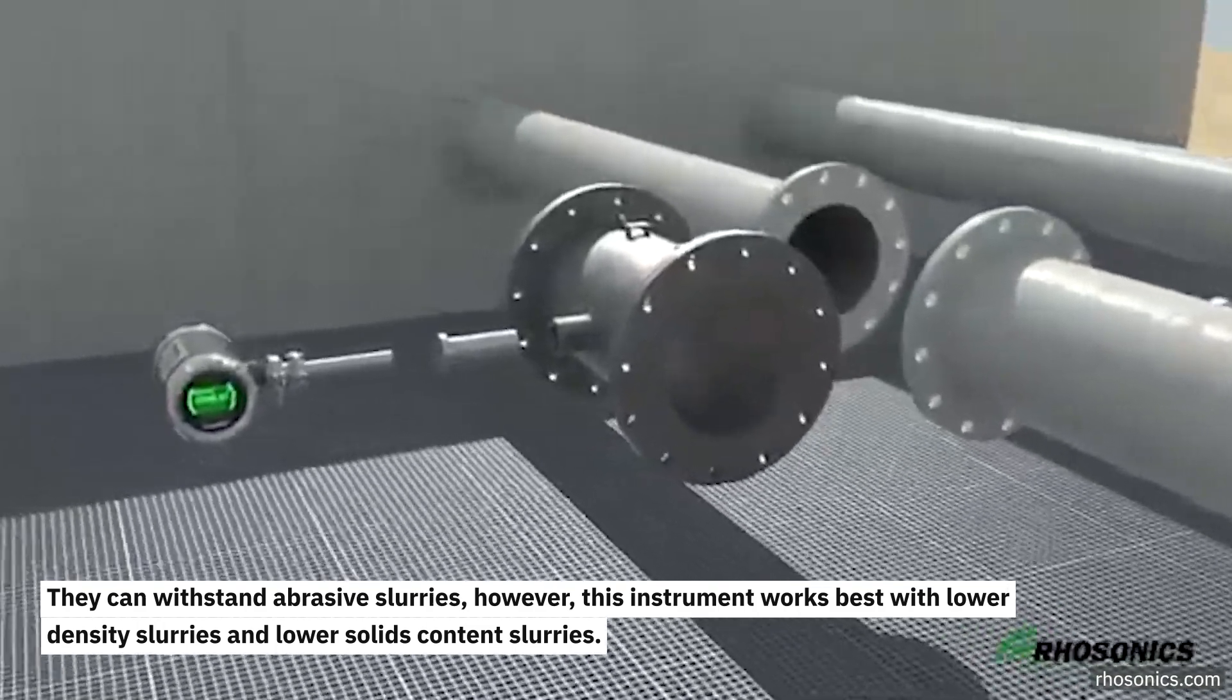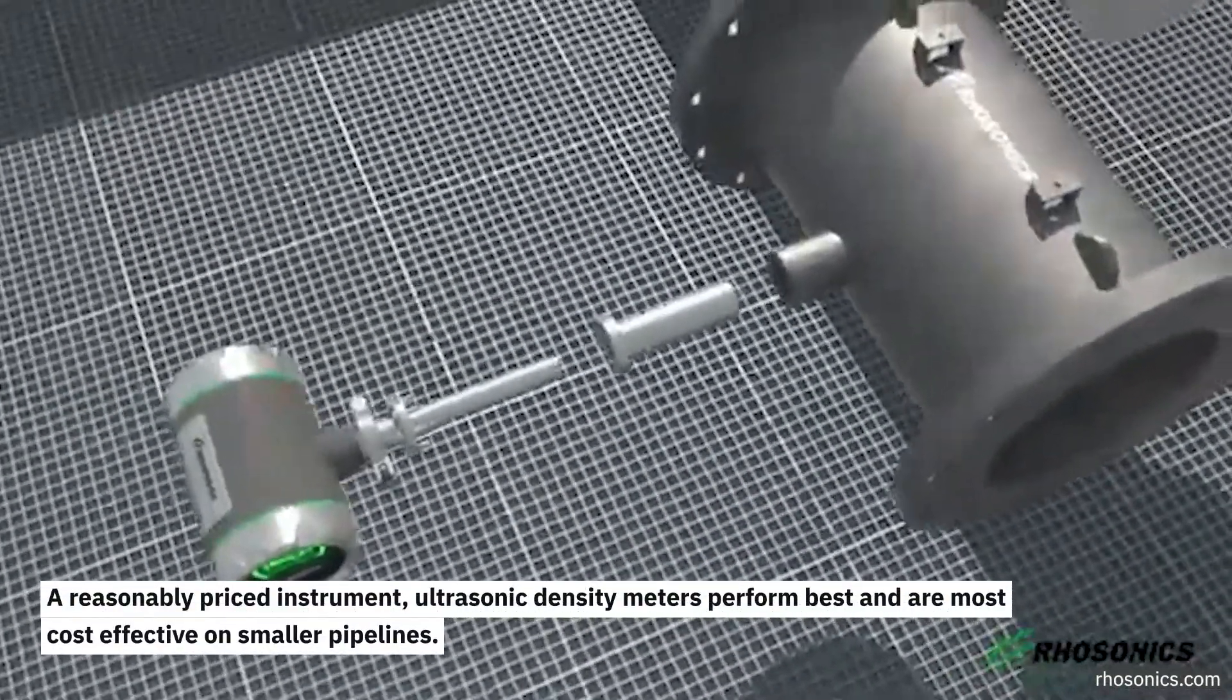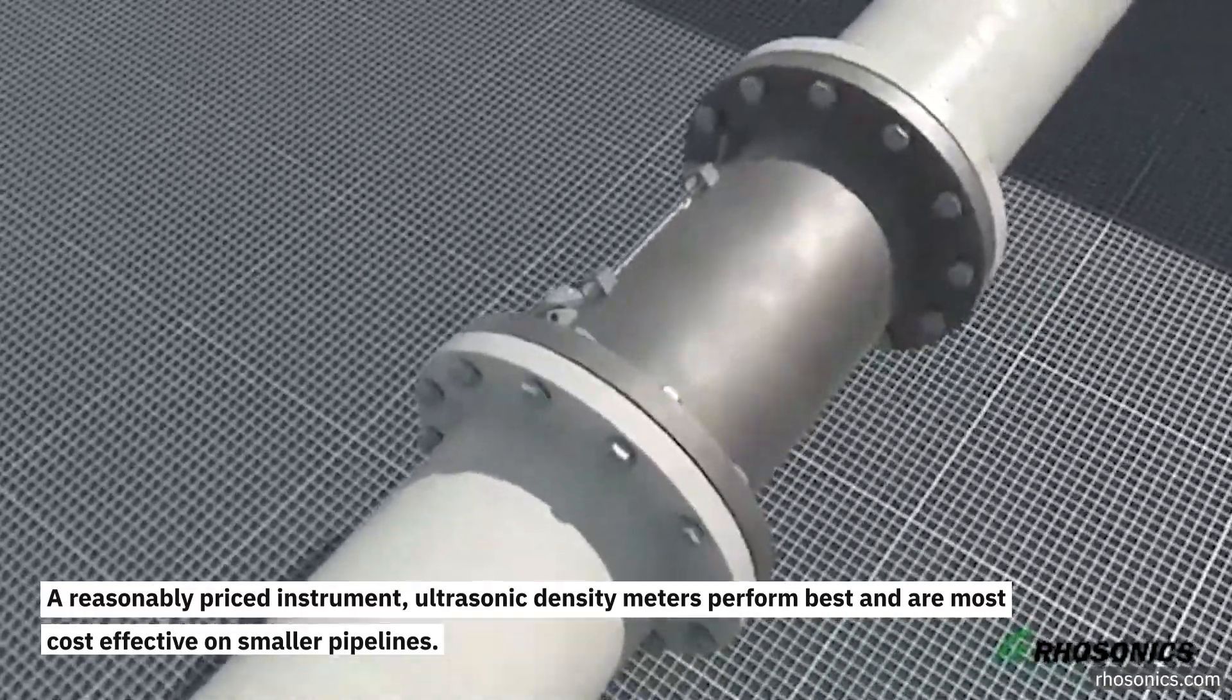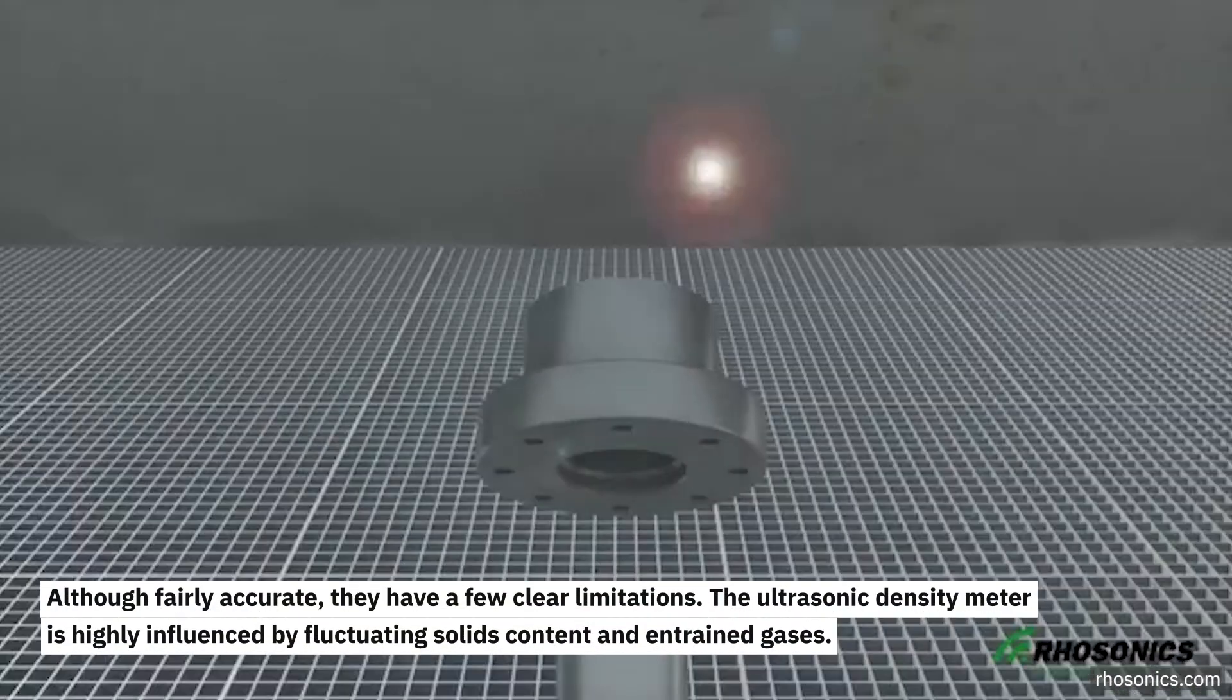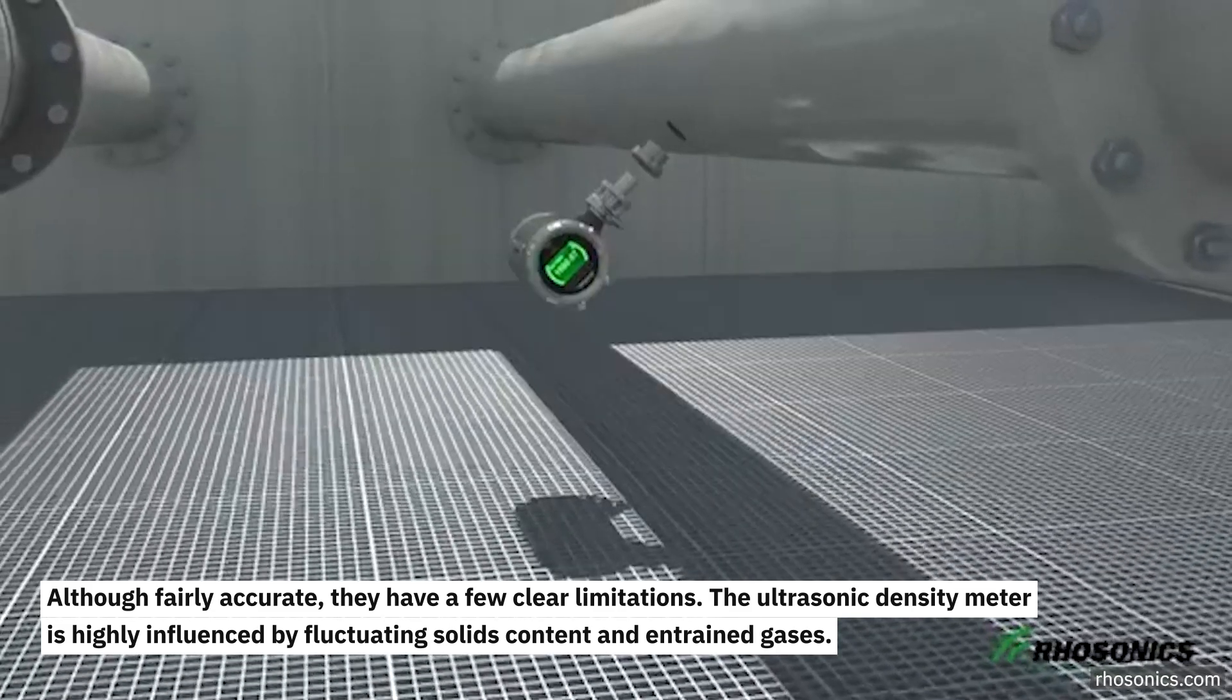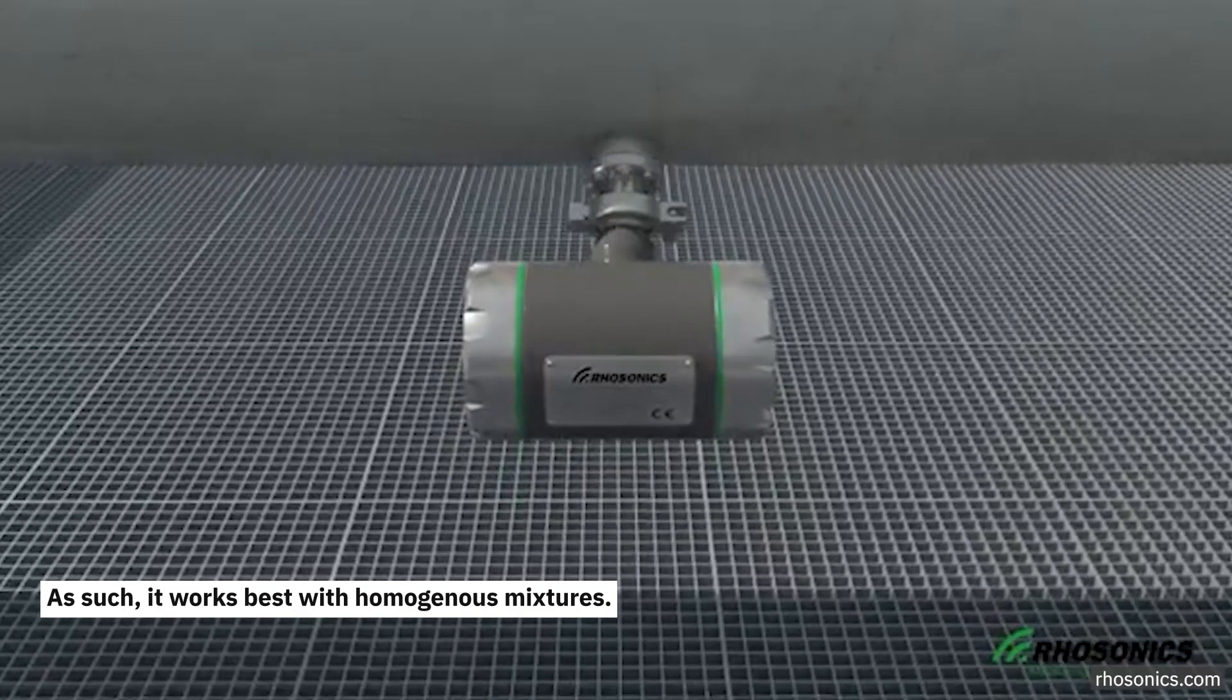A reasonably priced instrument, ultrasonic density meters perform best and are most cost-effective on smaller pipelines. Although fairly accurate, they have a few clear limitations. The ultrasonic density meter is highly influenced by fluctuating solids content and entrained gases. As such, it works best with homogeneous mixtures.